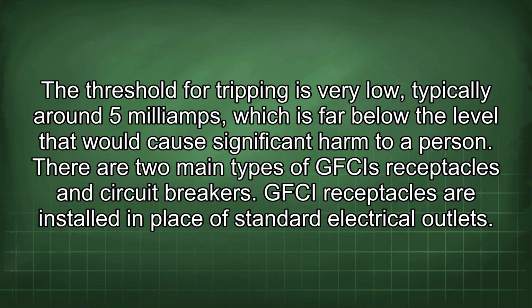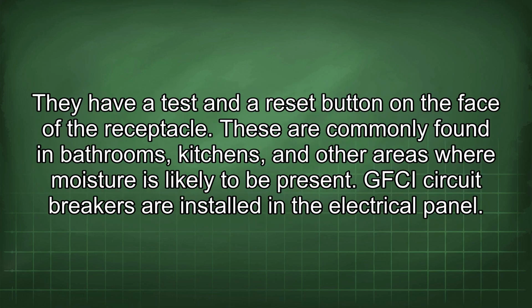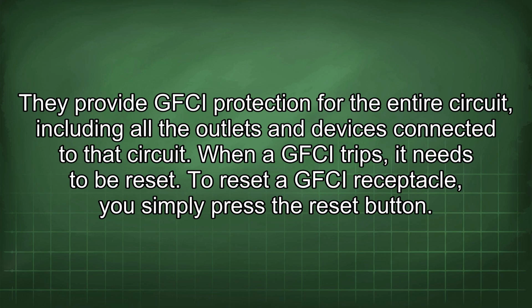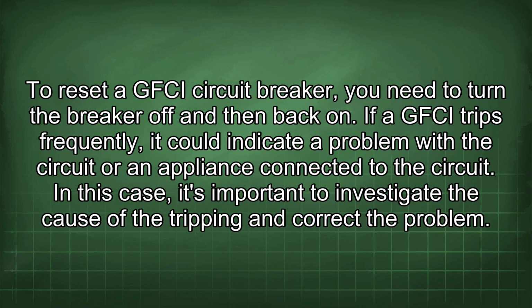There are two main types of GFCI receptacles and circuit breakers. GFCI receptacles are installed in place of standard electrical outlets. They have a test and a reset button on the face of the receptacle. These are commonly found in bathrooms, kitchens, and other areas where moisture is likely to be present. GFCI circuit breakers are installed in the electrical panel. They provide GFCI protection for the entire circuit, including all the outlets and devices connected to that circuit. When a GFCI trips, it needs to be reset. To reset a GFCI receptacle, you simply press the reset button. To reset a GFCI circuit breaker, you need to turn the breaker off and then back on.